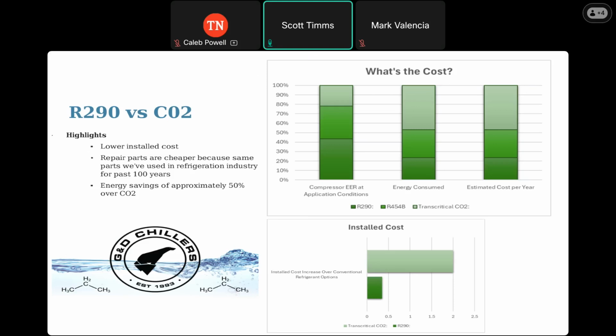So that leaves us with R290 and CO2. Comparing those two, on the right I have bar graphs comparing propane, 454B which is one of the current standard A2L refrigerants, and transcritical CO2, comparing installed cost, energy consumed, and cost per year. Propane is cheaper than CO2 by quite a bit. I have a slide later that speaks to the actual values.